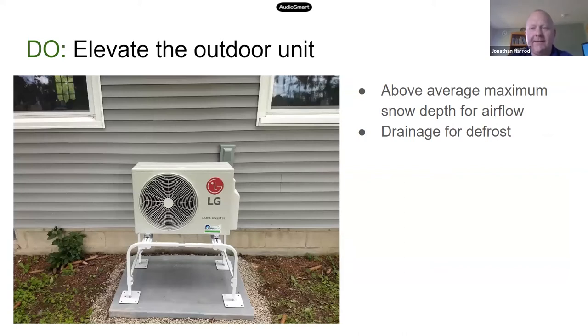Really important, and everyone who's a HeatSmart installer, I'm sure knows this by now, but it's really important to elevate the outdoor unit above the average snow depth. And the reason that's usually given for this is that you don't want snow drifts to pile up over the unit. These need airflow to function properly. So we need to keep bushes and fencing away from the unit, but we also need to elevate it high enough that it's not gonna end up buried in snow.